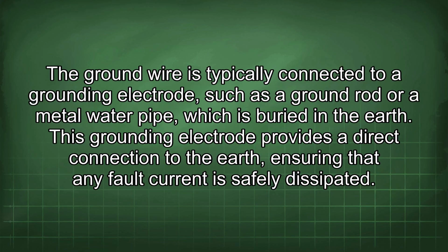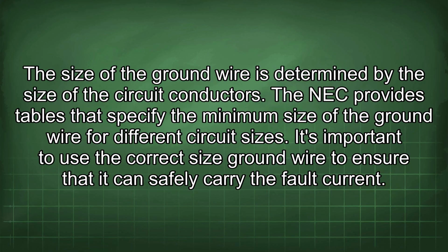The ground wire is typically connected to a grounding electrode, such as a ground rod or a metal water pipe, which is buried in the earth. This grounding electrode provides a direct connection to the earth, ensuring that any fault current is safely dissipated. The size of the ground wire is determined by the size of the circuit conductors. The NEC provides tables that specify the minimum size of the ground wire for different circuit sizes. It is important to use the correct size ground wire to ensure that it can safely carry the fault current.